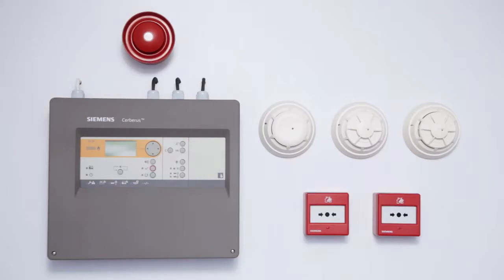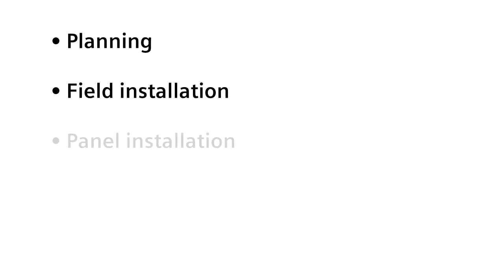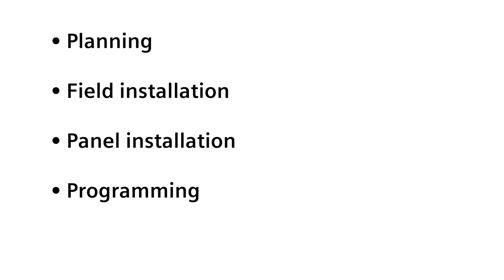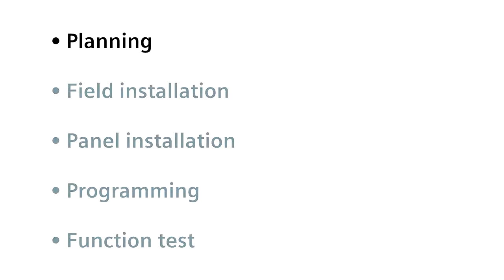The installation of the fire control panel should consist of the following steps: planning, field installation, panel installation, programming, and function test. The planning should consist of assigning the field devices to the floor plan as per local regulations, documenting the panel parameters, calculating the battery's standby time. Given that the code of practice for planning a fire detection system is different from country to country, the planning step will not be discussed in this video.